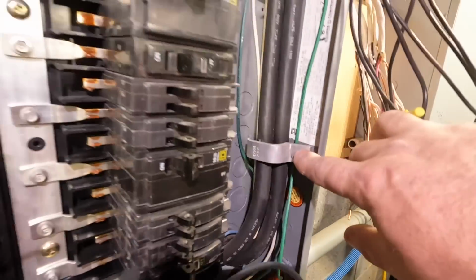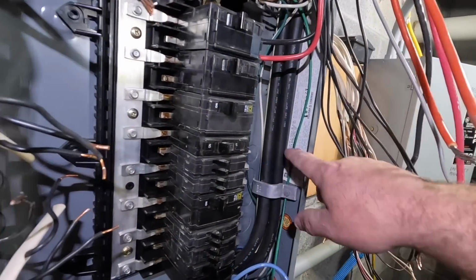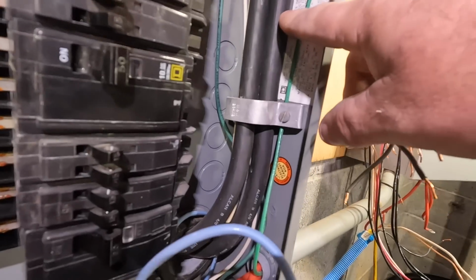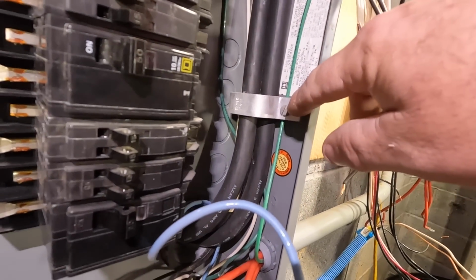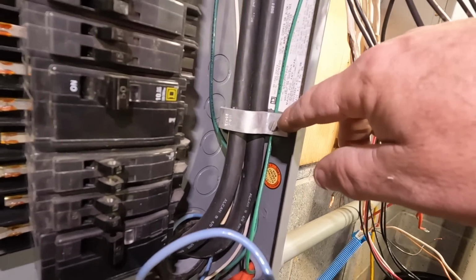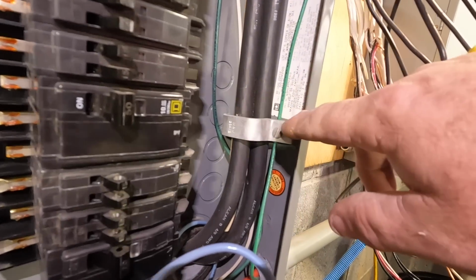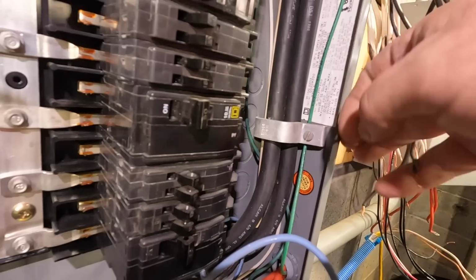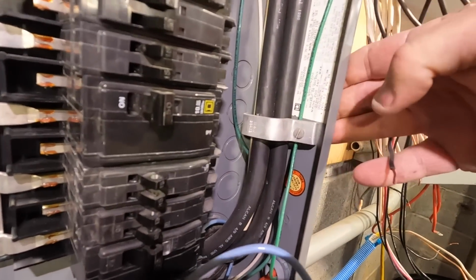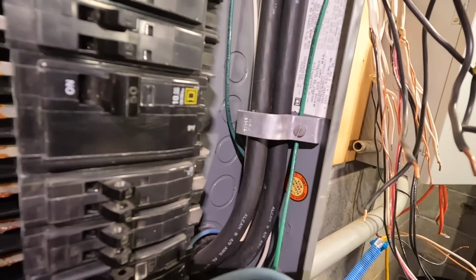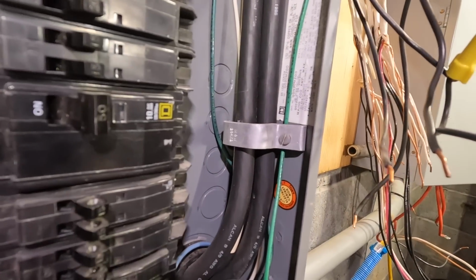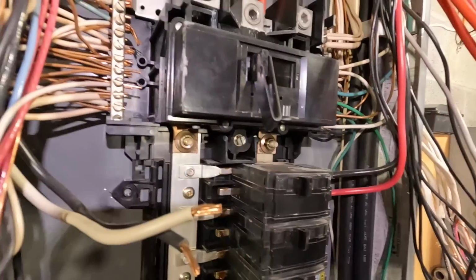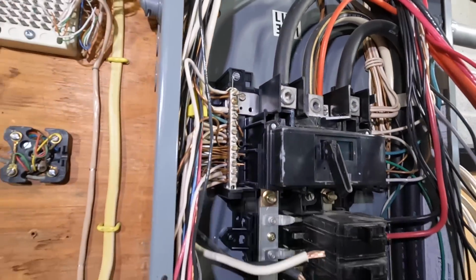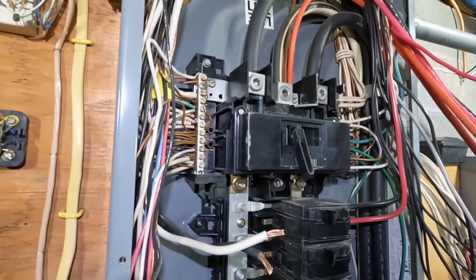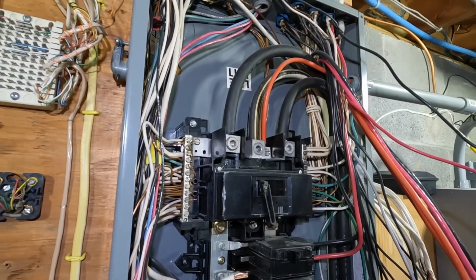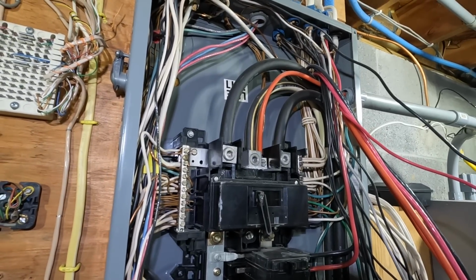This is a strap inside the main breaker enclosure, holding down the service entrance conductors. I don't know, that to me isn't safe, because this metal could bite into this, and now you're connected. You got the screw right to the enclosure here. That's a major short circuit waiting to happen, or ground fault waiting to happen. I don't know why they would do that, but I gotta go upstairs and pull the meter, and then the service entrance conductors will be dead, and this whole panel, whole house would be isolated from the service. So let's go outside and pull that meter.